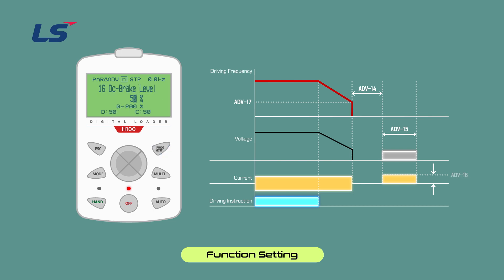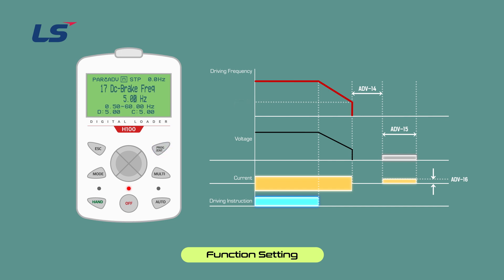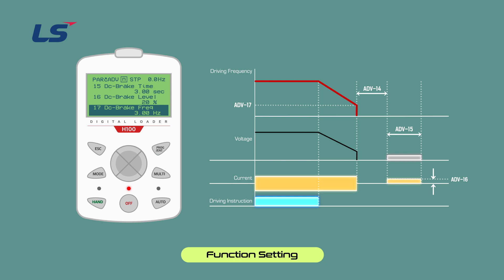When you press the Enter key in ADV16 DC brake level, a screen where you can set the DC braking amount will appear. Use the direction keys to set and press the Enter key to complete the setting. When you press the Enter key in ADV17 DC brake frequency, a screen where you can set the frequency will appear. Use the direction keys to set and press the Enter key to complete the setting. The DC braking start frequency can be set to 0 to 60 Hz depending on the equipment condition.